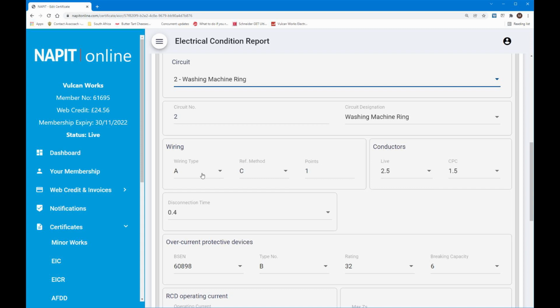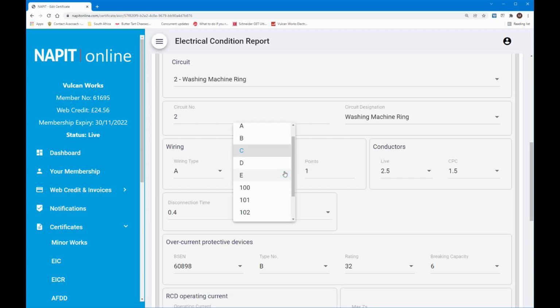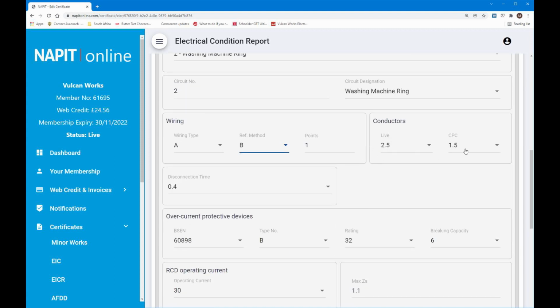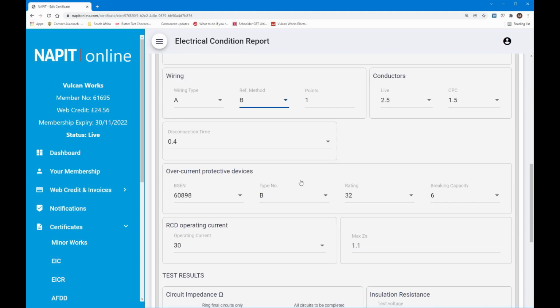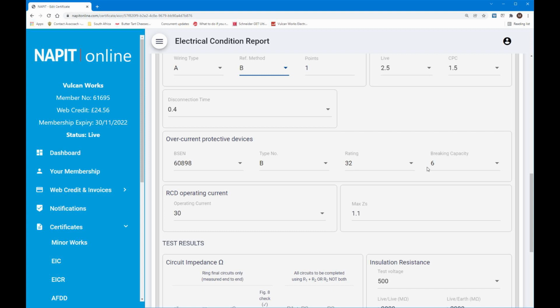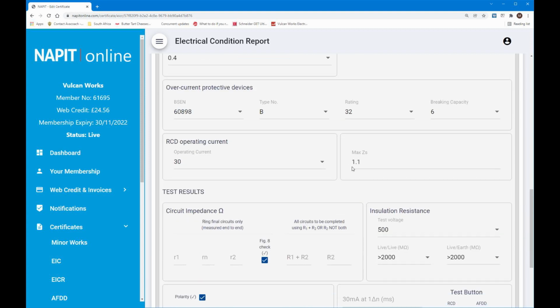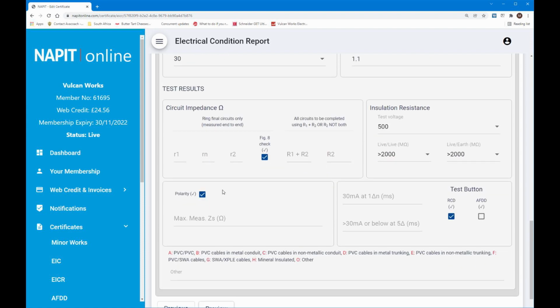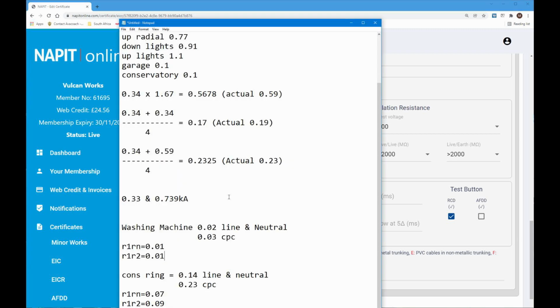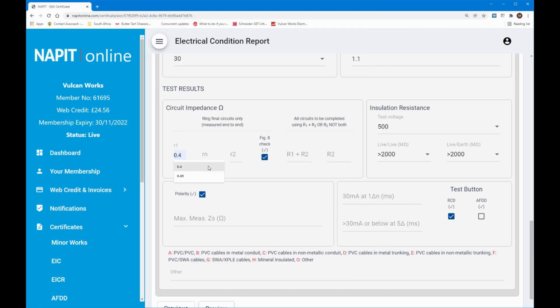So we come down here and it's a type A. The washing machine ring was type C, although it was in, actually it's not type C, I've got that wrong in fact, because it was in conduit if I remember correctly. It's type B in fact. Do apologise, and there's only 1 point. And it was 2.5 and 1.5 for the conductors, 0.4 disconnection time, had a 32 amp rating, 6 kA breaking capacity, and 1.1 ZS. So again we come down to the R1, Rn and R2 readings. So we came down here and the washing machine readings were 0.02. So we are going to put them in anyway.